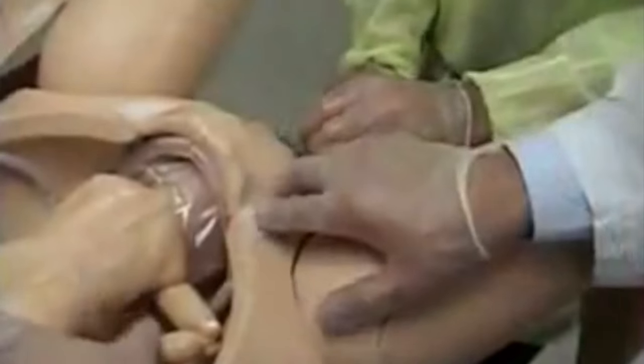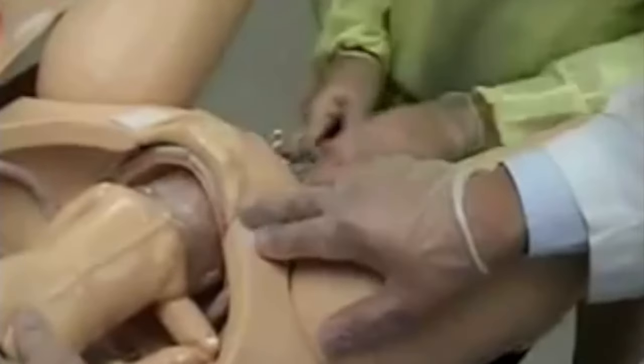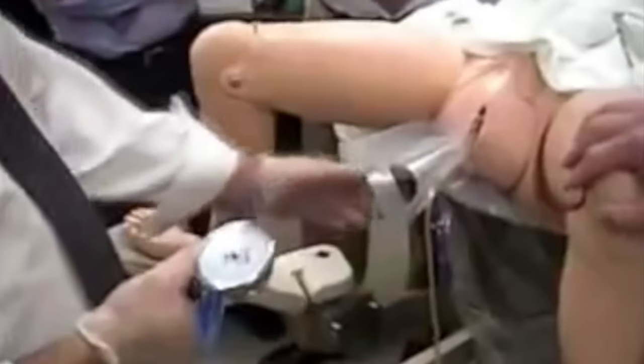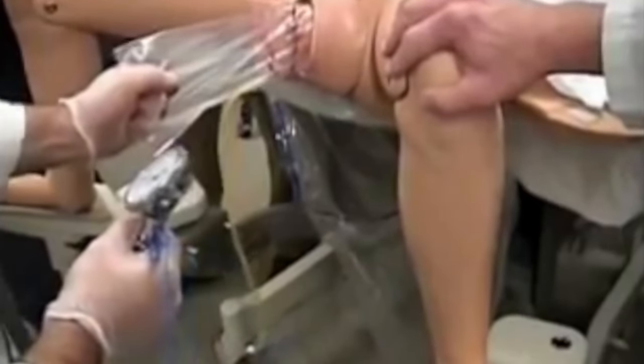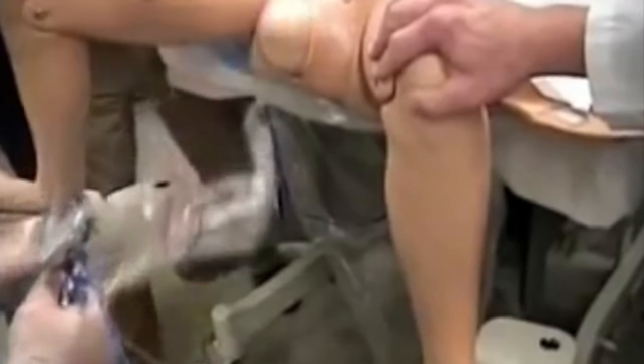The following video shows the application of the device on a mannequin. The device is introduced with a thin flexible spatula. When a minimal amount of air is insufflated via a tubing with a valve, the air clamp is achieved. This results in a sealing effect between the fetal head and the maternal birth canal. Traction on the bag, which embraces the entire fetal head, brings about extraction of the head. The valve of the tubing is then opened to deflate the bag, which is then removed and the head delivered manually.